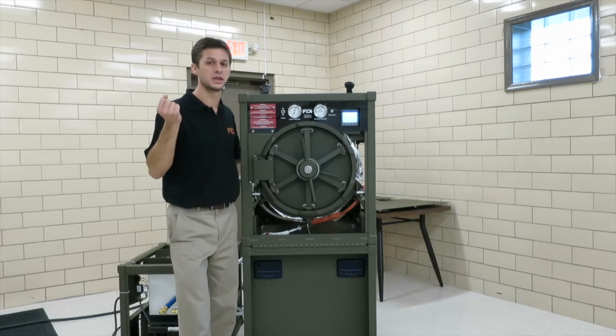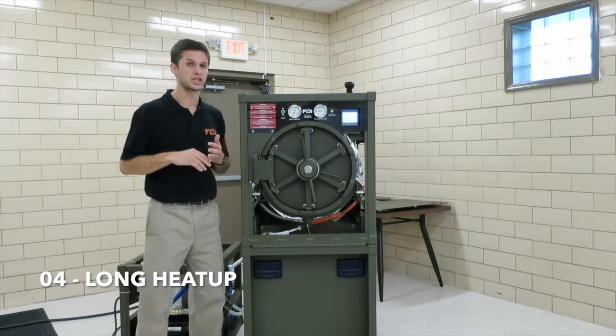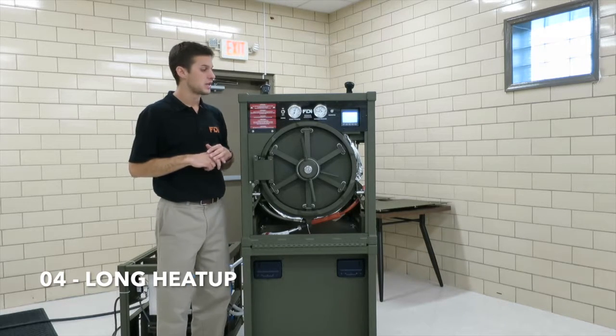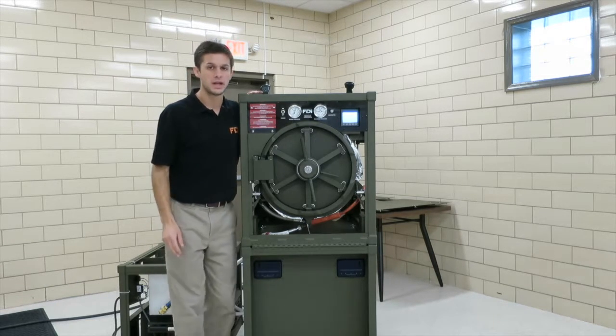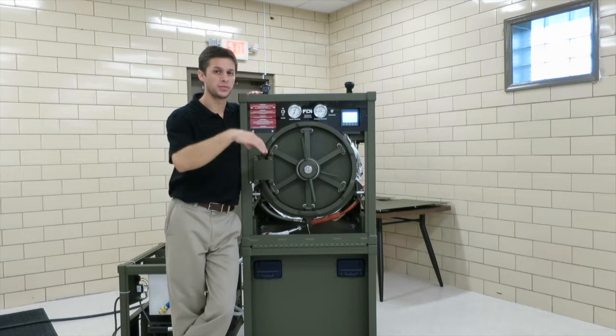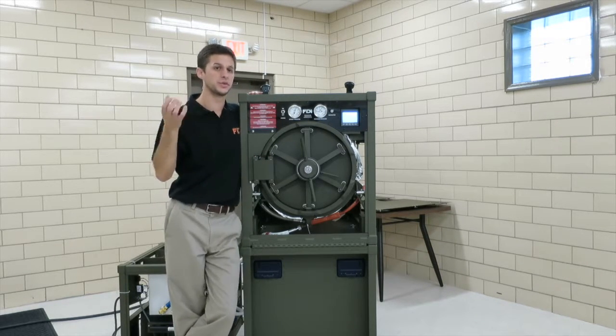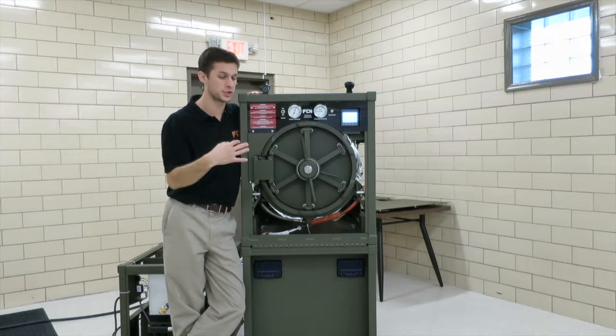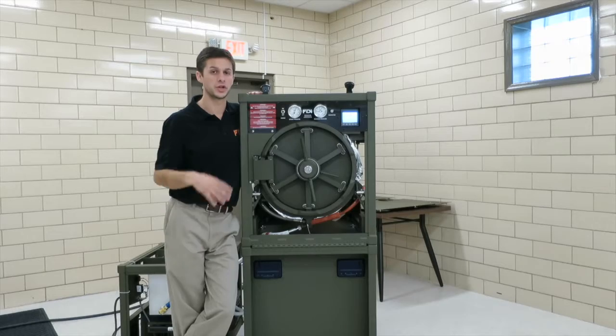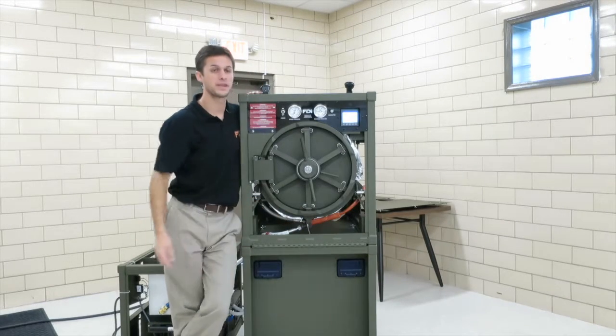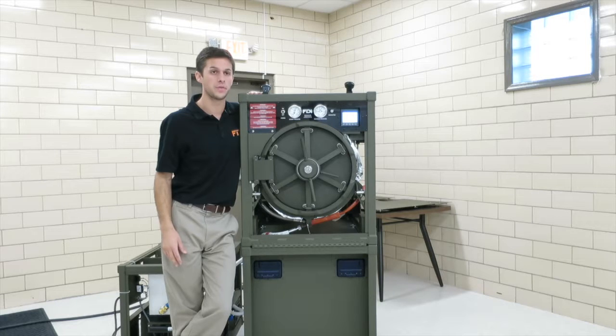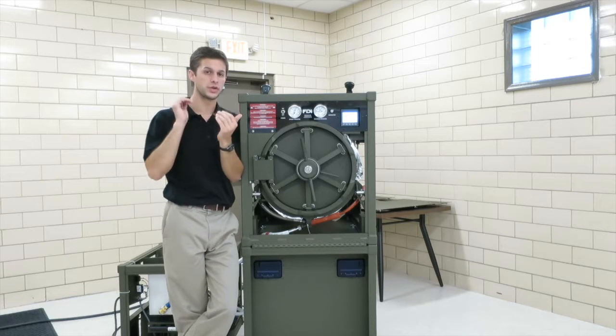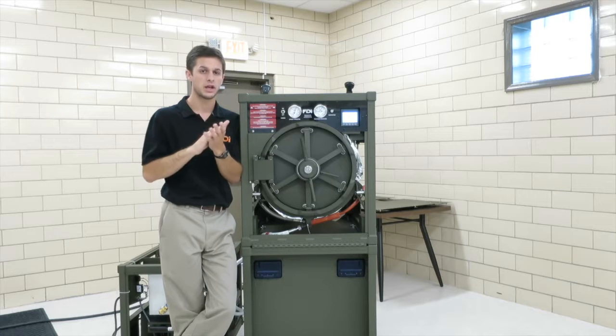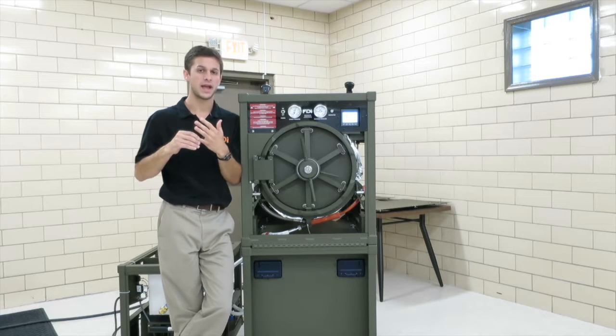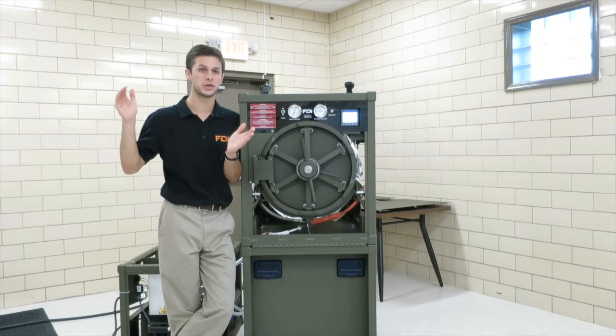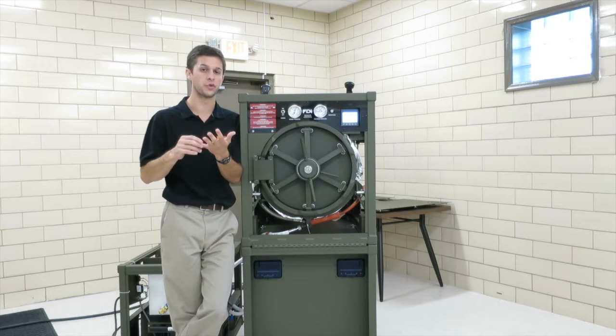The 04 alarm is the long heat up. It's a little different than the jacket warm-up slow. The long heat up alarm is for during cycles. After you go through your conditioning phase, your pressure pulses, your vacuum pulses, you get to the heat up, where you switch to temperature control, controlling off of the temperature in the RTD probe down here in the drain. When you switch to temperature control, that heat up to 273 degrees should take a pretty standard amount of time. Again, there's a watchdog timer. If that's taking longer than normal, you will get a long heat up 04 alarm.